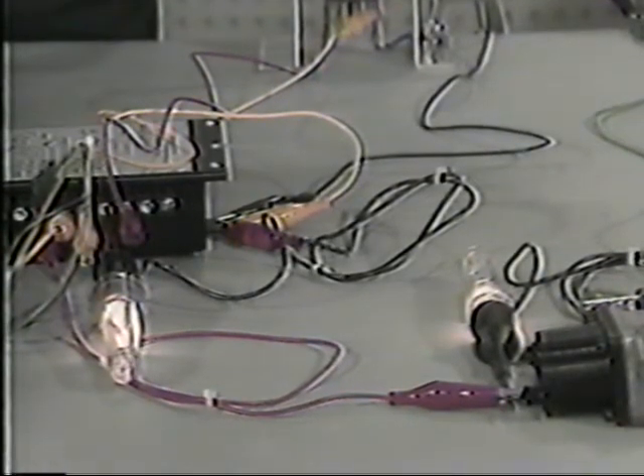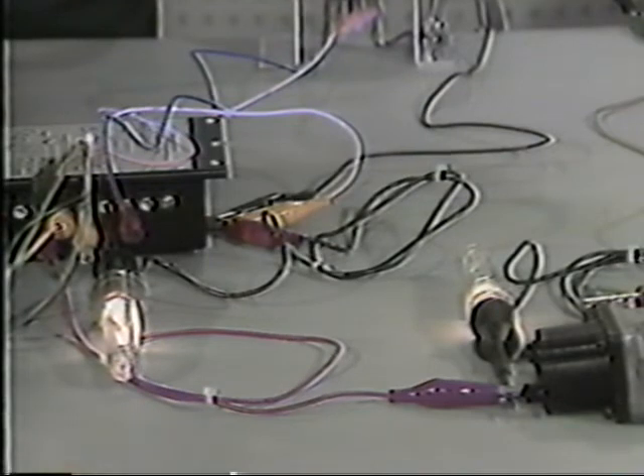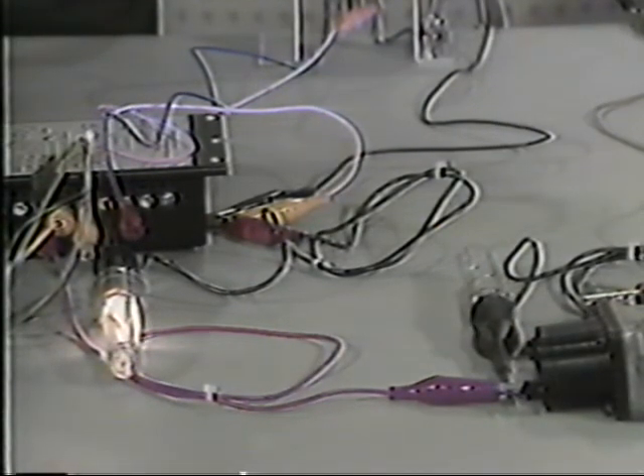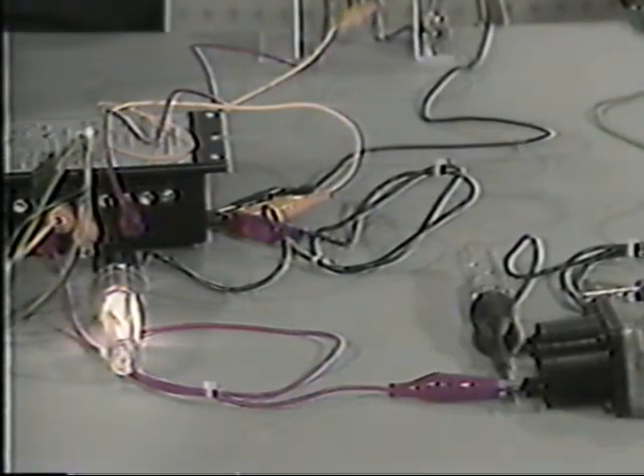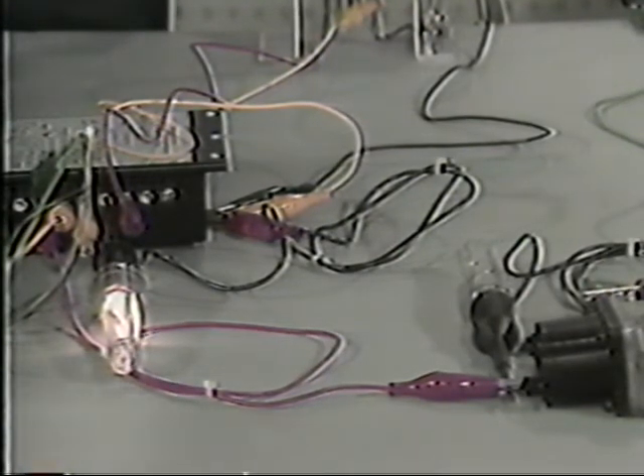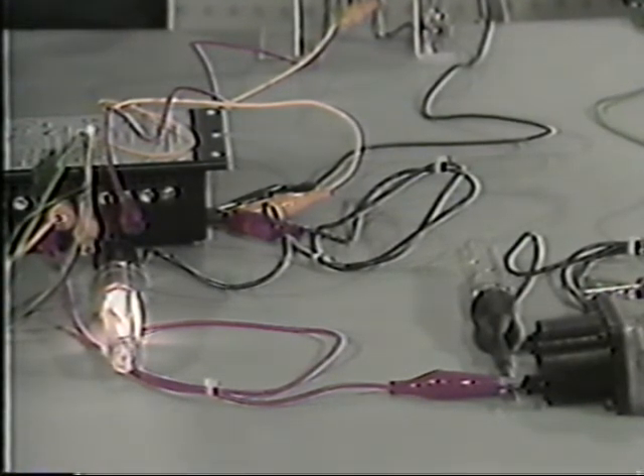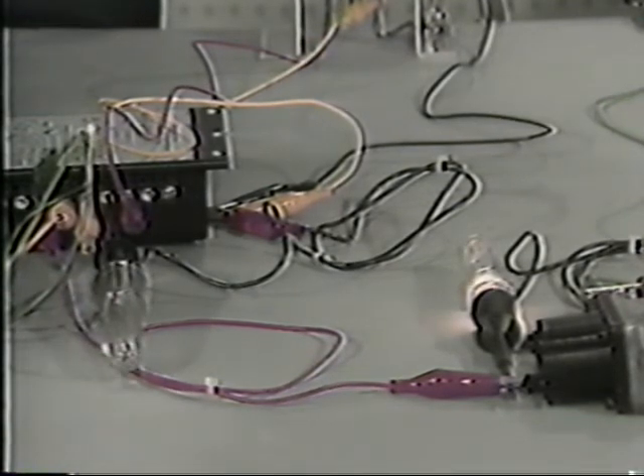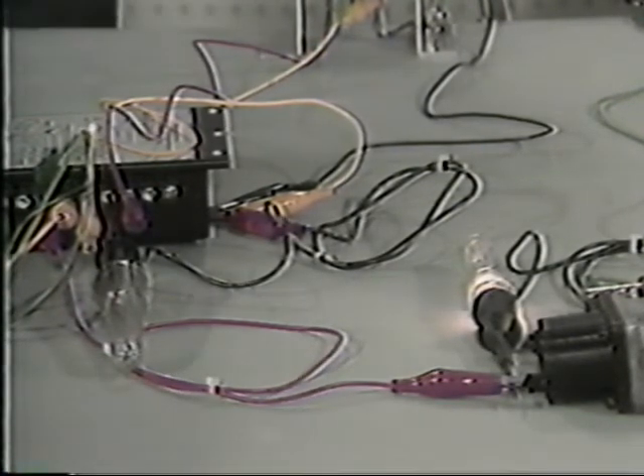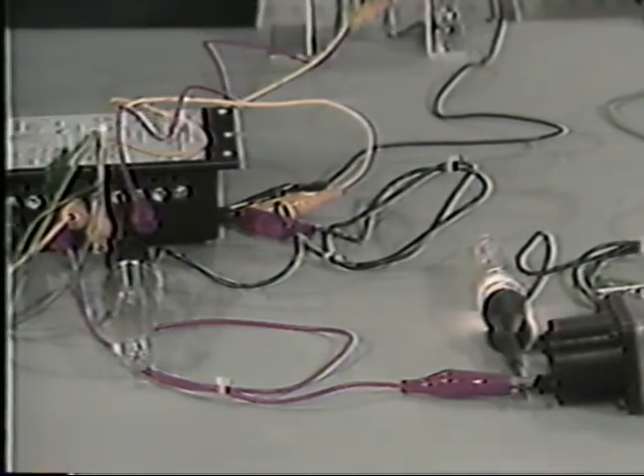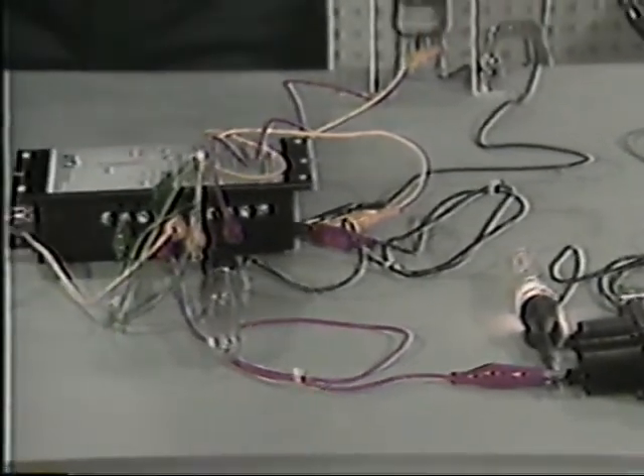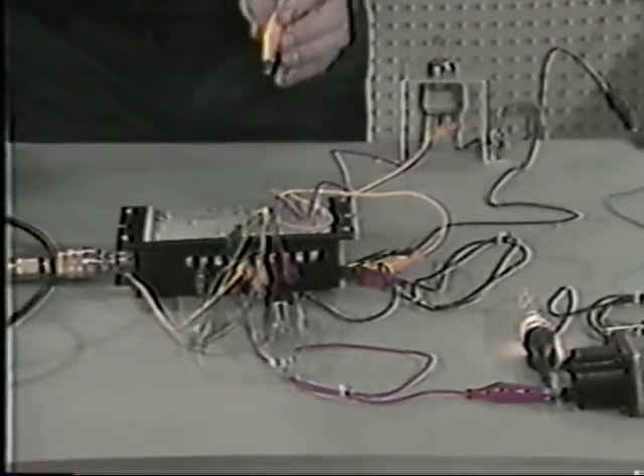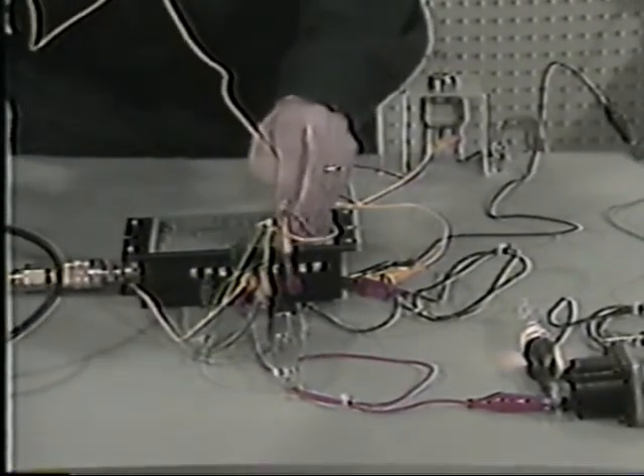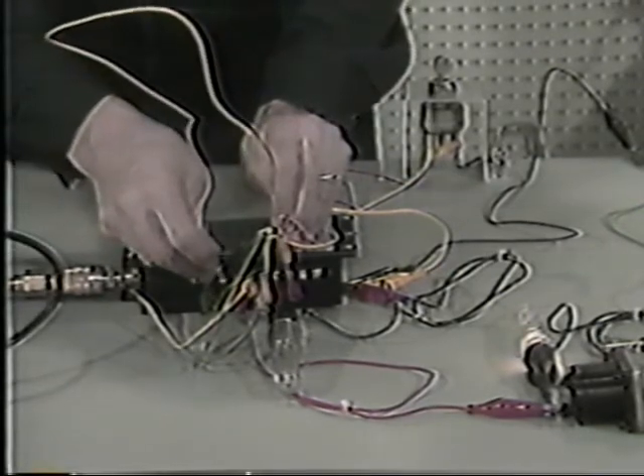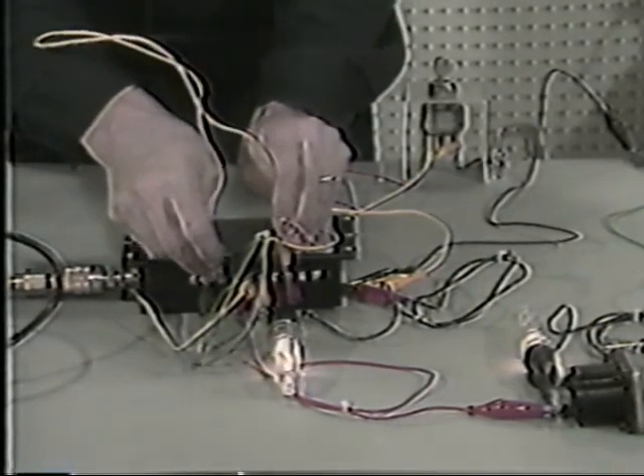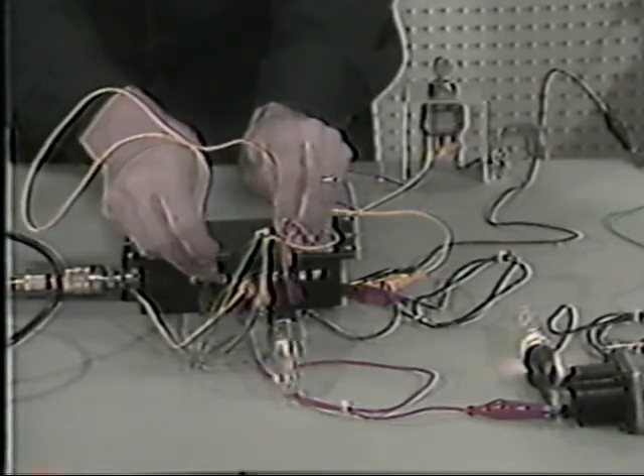And it does. Continue to vent the air pressure until we reach the shutdown setting, which on this unit is 15 pounds, and note that the fuel solenoid once again turns off. For a second time, raise the air pressure back to above 25 pounds, and the condition should reverse. Next test, connect battery positive to the NO terminal on the module. This is the 7th one down next to the end. When you do this, the warning test light should come on every time you make the connection.